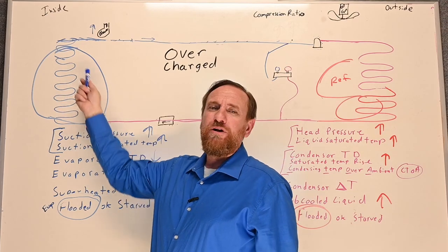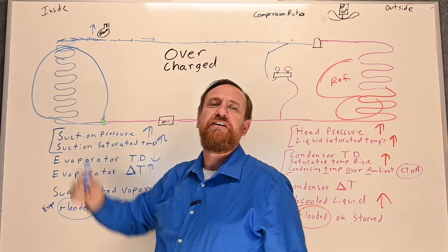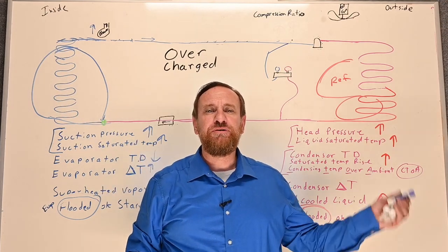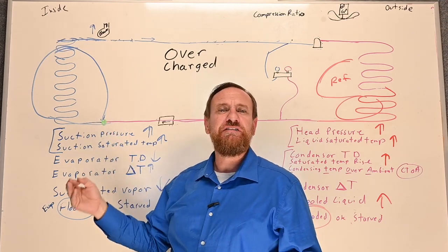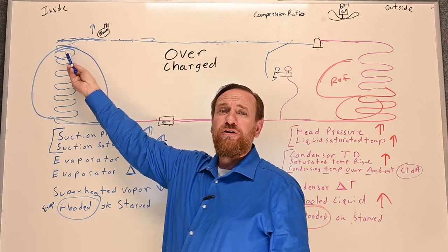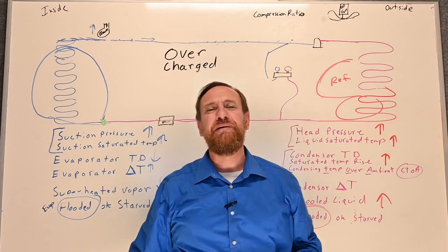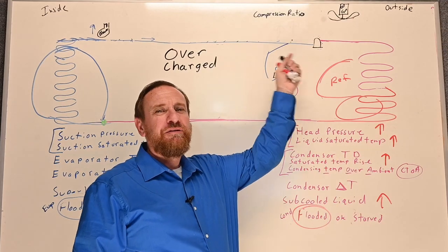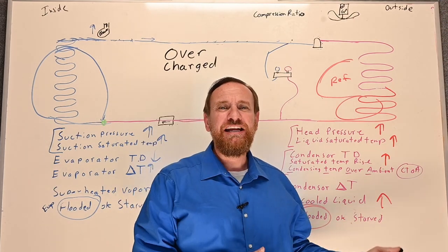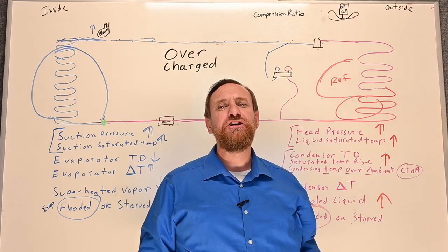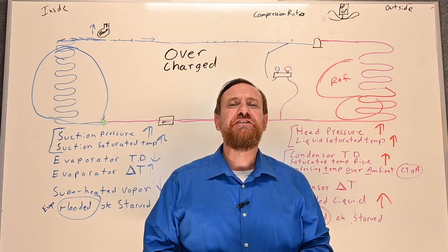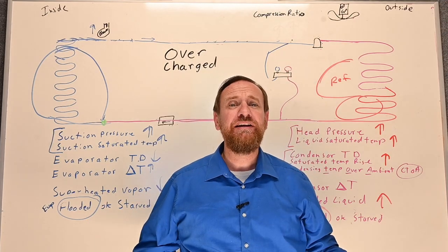Now that we end up with more and more refrigerant in our evaporator coil, it's easy to overfill it and end up with liquid refrigerant running through the suction line. Even if it's not happening right now, what happens when conditions change — outdoor or indoor temperature shifts? Because it's a fixed metering device, it's at the mercy of all those conditions. When we overfill that evaporator coil, we get liquid refrigerant or a saturated mixture to our vapor pump — the compressor. It washes the oil away from the bearings, hits the windings and breaks them down, causes the oil to foam, and we end up trying to compress liquid, causing valve damage. Tons of damage — and it doesn't happen right away, it takes time.